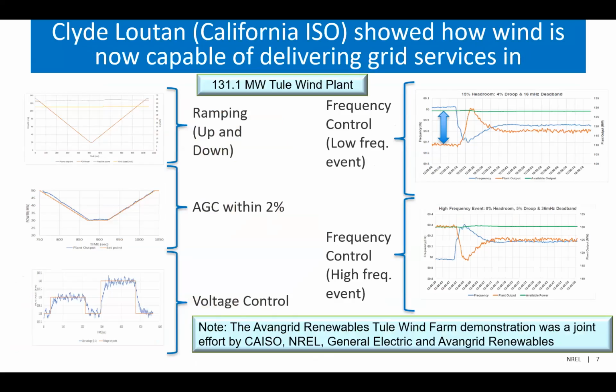Looking at system assets and system control, Clyde Loutan gave a presentation a few weeks ago during this workshop showing results from a campaign with a 131.1 megawatt plant in California, using it to deliver a variety of system services. They showed this plant could deliver ramping both up and down very accurately, perform automatic generation control within a 2% error bound, and provide voltage control and frequency control both up and down. So there's already the ability of these wind plants to deliver things that will be necessary more broadly.